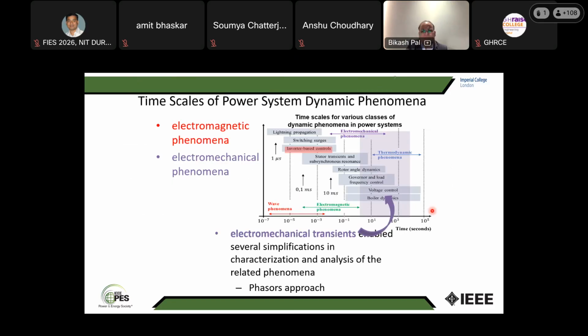So how do we do that? Okay, now let's take a look at the time scales of power system dynamics phenomena. We have been talking about rotor angle dynamics. This is on the order of 10 to the power of 1 seconds. So 10 seconds means 1 by 10 is 0.1 hertz. Now if I go here, say 5 seconds, then 1 by 5 is 0.2 hertz. And if I go to 1 second, 1 by 1 is 1 hertz. So the electromechanical oscillation is in this time scale.